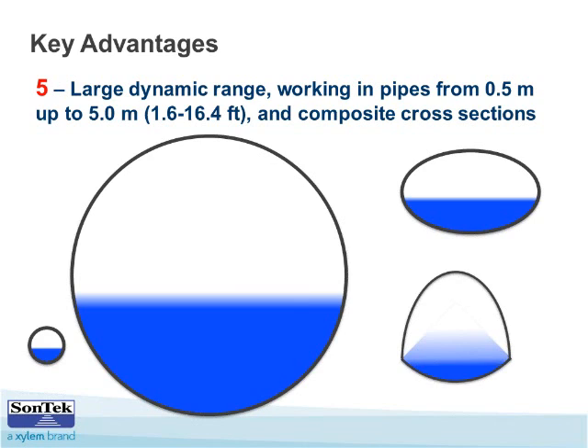I think this is an asset, especially in the irrigation market, where some delivery pipes that have moved water over many years or decades have changed shape and become very non-symmetrical. Something key in the installation is to make many different measurements to ensure that the pipe is true. If it's not, you measure that and input it into the XY data for the area, and it will accommodate it. So it's very flexible, and it will accommodate any shape or irregularity of that pipe or open channel.